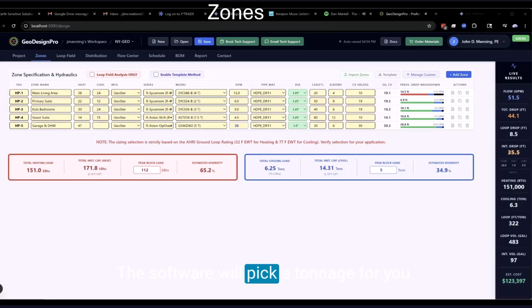The software will pick a tonnage for you, but I caution you, this is based on the AHRI closed loop rating. So if your application is significantly different, then you can override the choice the software made and pick any size you'd like. You've got flow rates, pipe material, diameters, length, number of elbows, and a CV value for typically a two-way valve. You may have strainers. If both a two-way valve and a strainer, you put the CVs of both separated by a comma, and it will calculate an equivalent CV.